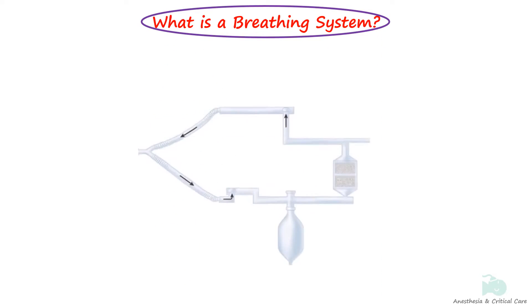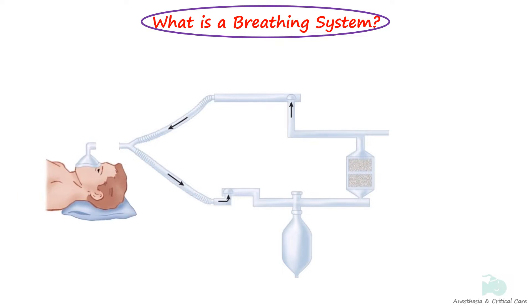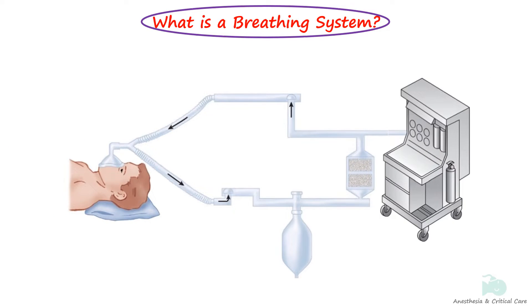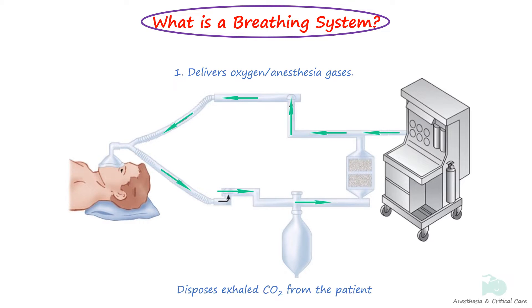The breathing system is an assembly of components which connects the patient's airway to the anesthesia machine. This creates an artificial atmosphere from and into which the patient breathes. All anesthesia breathing systems have two fundamental purposes: first, it delivers oxygen and anesthetic gases to the patient, and secondly, it eliminates carbon dioxide either by washout with adequate fresh gas flow or by carbon dioxide absorption.